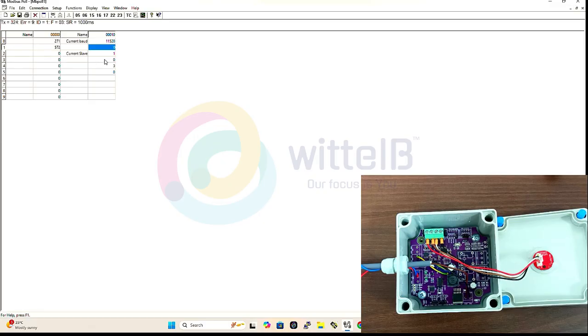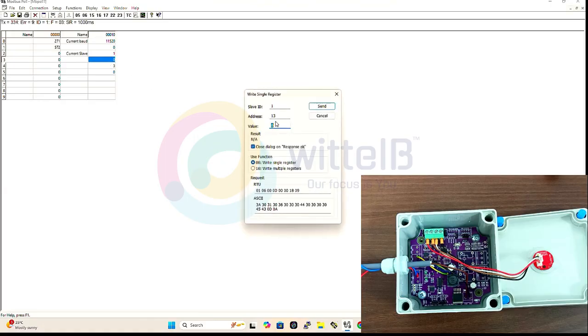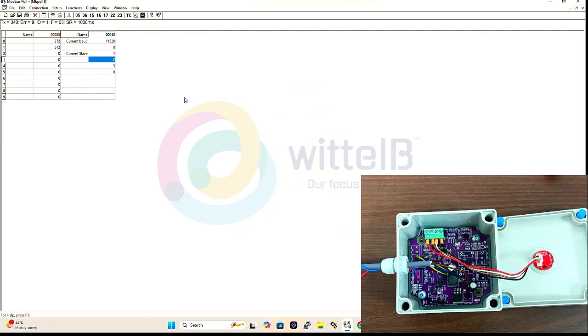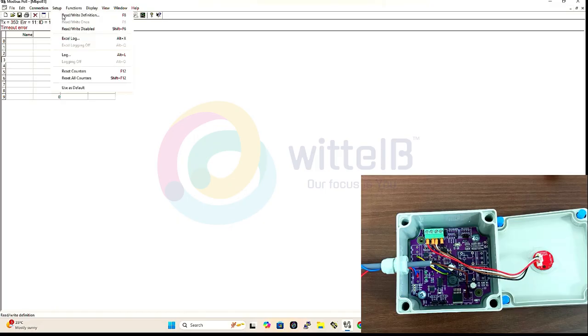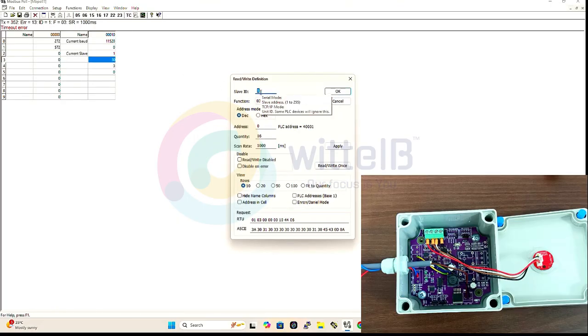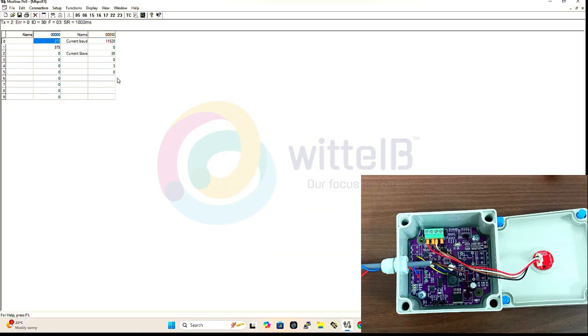Now I want to set the slave ID as 30. Here we have the current slave ID, that is 1, and I need to change it. Below we can set the slave ID. Double click on that and provide the required slave ID, that is 30. Otherwise you can set your own slave ID, and send the request. The request has been sent properly. Now I need to bring the board up with the new slave ID. Just press the reset. Here I will get the timeout error. Now go to the setup directly and click on read and write. Provide the slave ID as 30, which was set by the user, and okay. See, the board has connected with the new baud rate and the new slave ID. And according to this, you can set other slave IDs also.